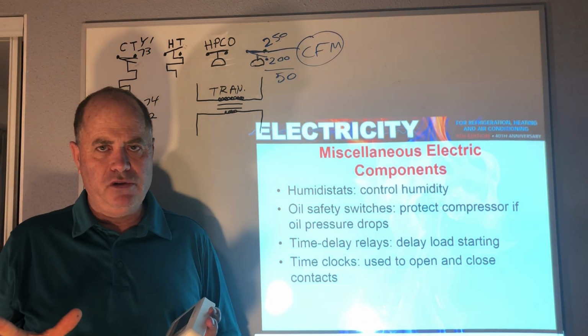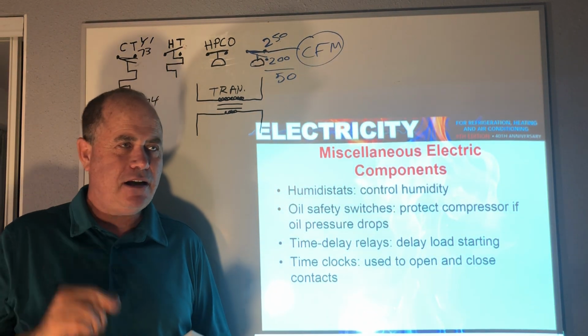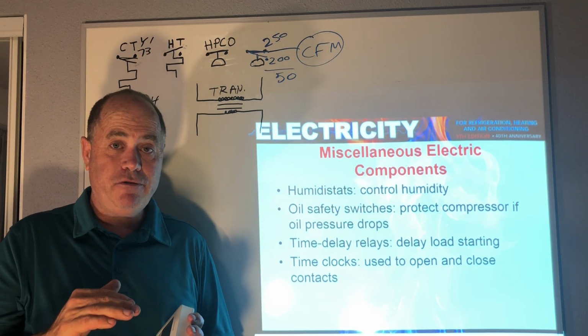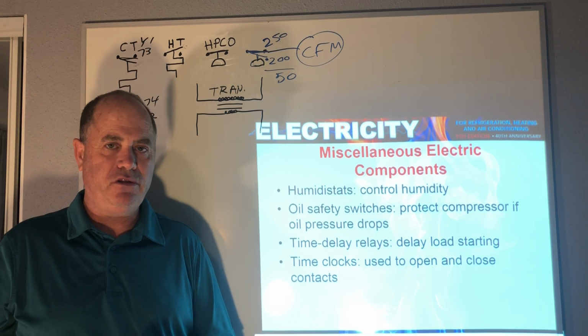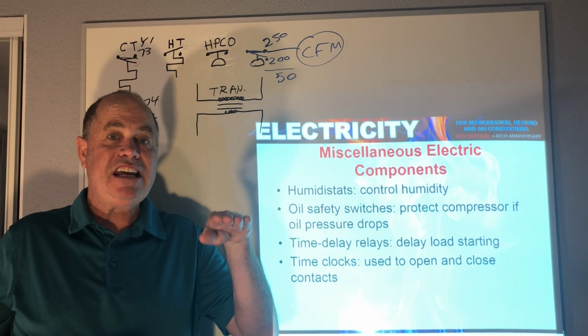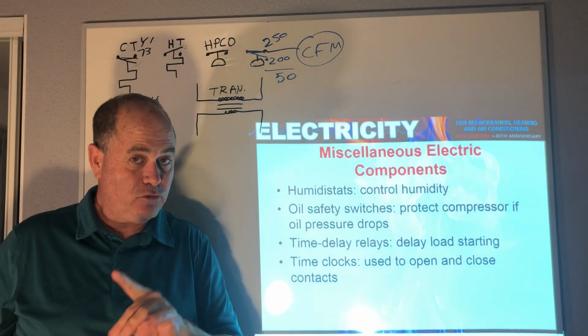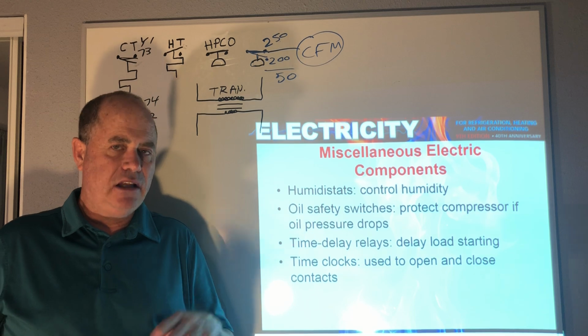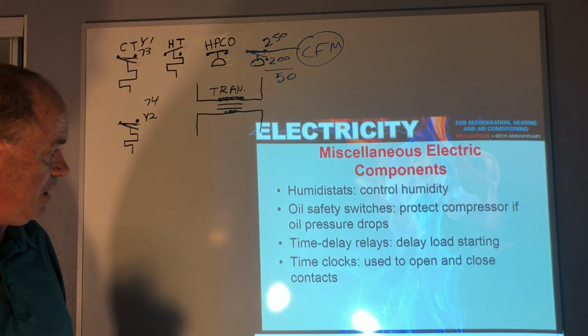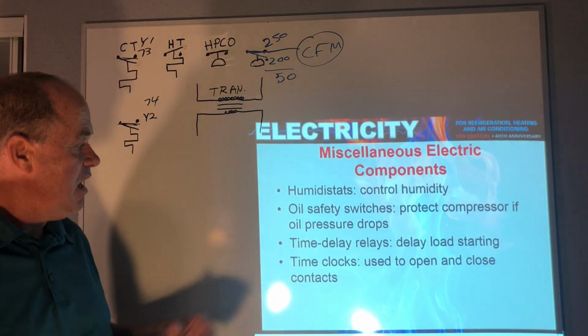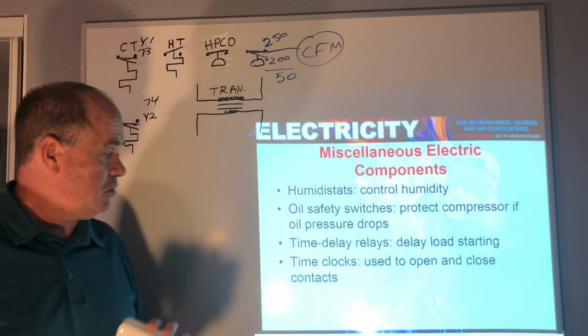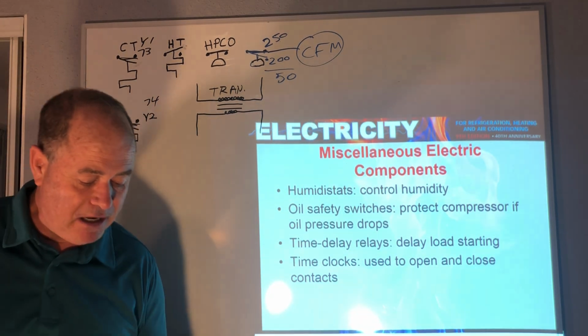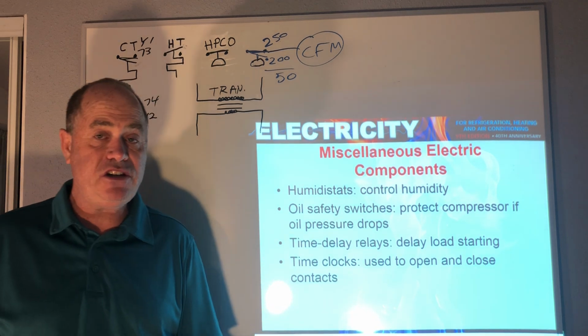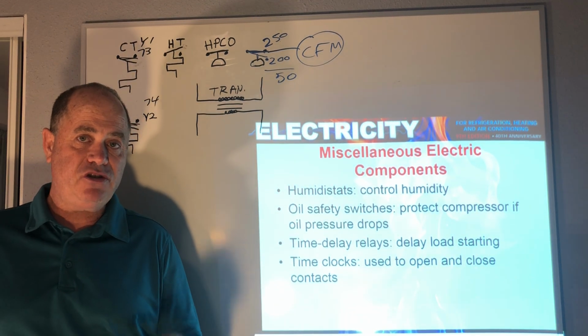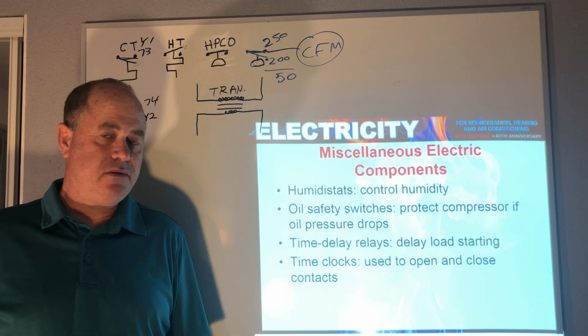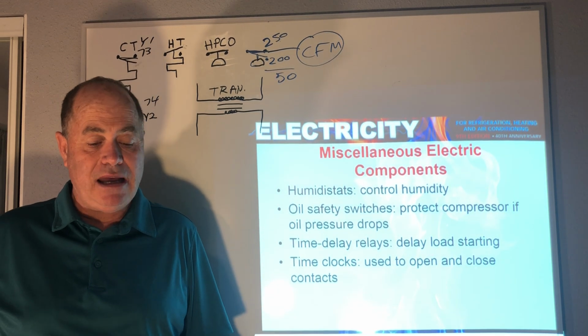One of my rules, like the 10 commandments of air conditioning and refrigeration, is that once the compressor stops, never restart it for 2 or 3 minutes, in order to let the pressures equalize as much as possible. They almost never totally equalize, and it also lets the compressor and the windings cool down a little bit. A lot of times that's built into the thermostats nowadays, and time clocks are also built into thermostats and or circuit boards. But we still use manual time clocks for things like freezers that have defrost timer motors that bring on big heaters to defrost the evaporator coils at certain times.